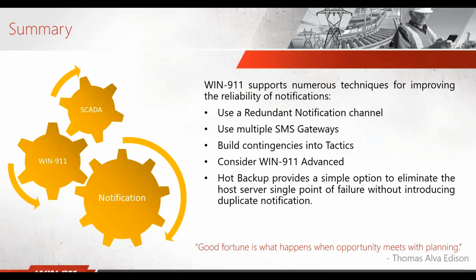So in summary, Win911 supports numerous techniques for improving reliability of notifications. We recommend using that redundant notification channel. Again, if you are setting up Win911, it's always a great idea to have 2 notification types in case one does fail. Use multiple SMS gateways if you are using SMS. If one modem has an issue, the other one can take over and start sending messages out through that gateway.